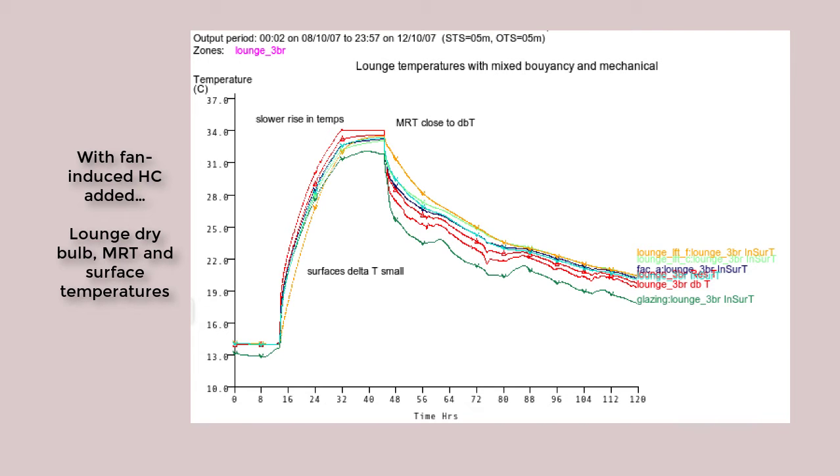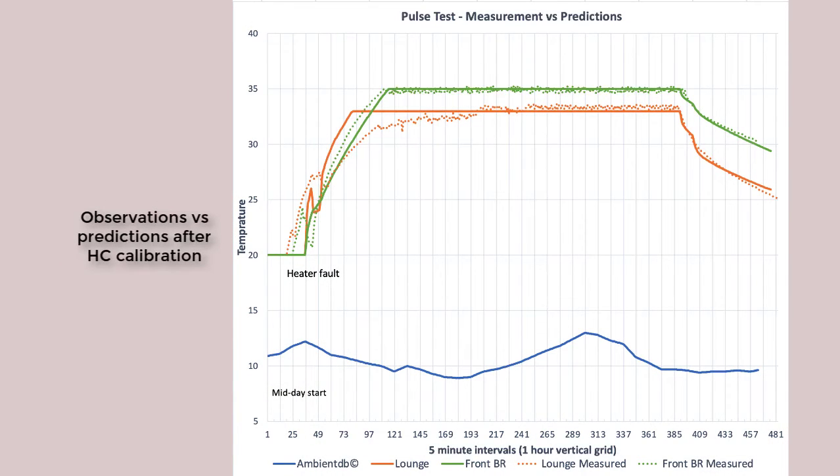The corrective action was to impose heat transfer rates based on the observed air velocity when the fans were operating. So in an extreme case, getting the heat transfer regime aligned with conditions in the room is critical to improving the predictions of the digital twin.